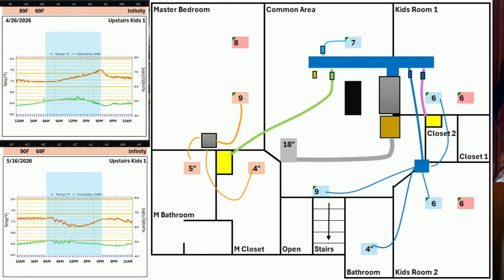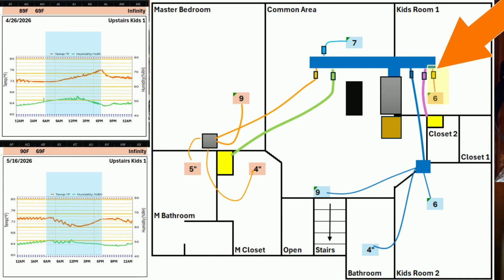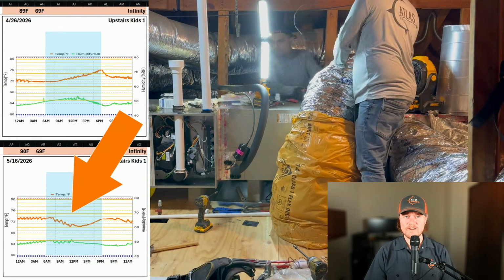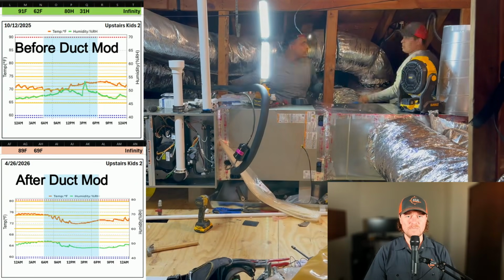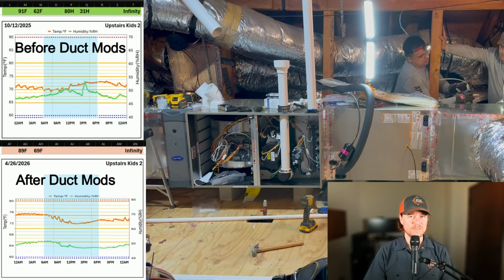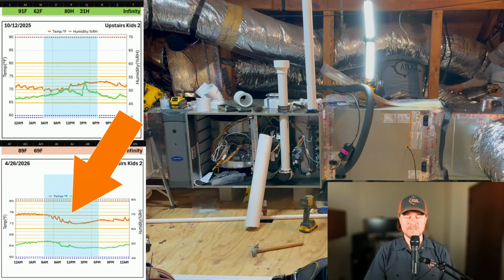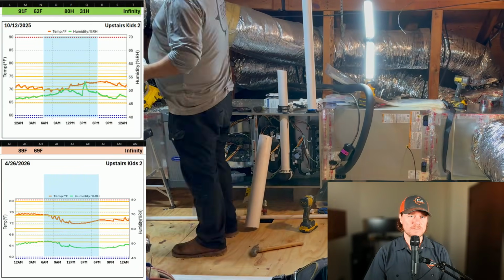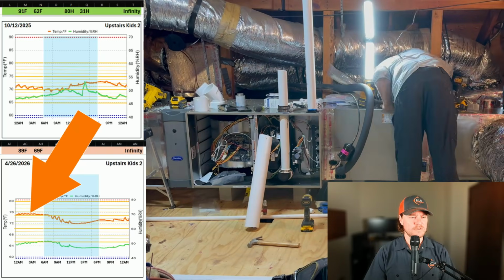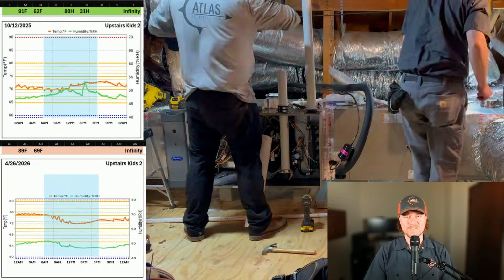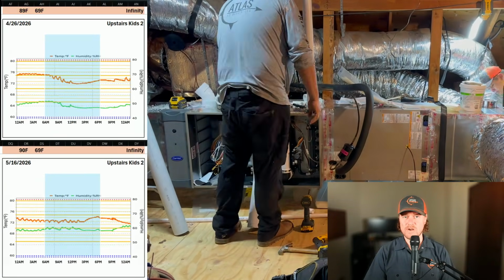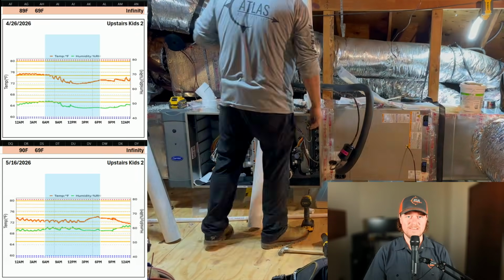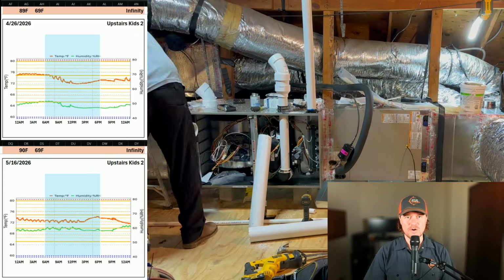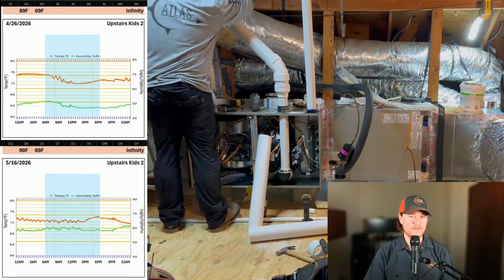What I ended up doing is rerouting that duct altogether from the distro box and connecting it directly to the supply trunk. That way I could fully utilize that duct and get the max amount of CFM out of it. And that did the trick. And in my son's room, after doing the duct modifications, it created a problem. You can see here on this day, I had the temperature set at 72 degrees, and in his room, it's getting pretty close to 76 degrees. What I ended up doing is dampering down the 9-inch over the stairwell, which is tied to the same distro box, and that directed more airflow to his room, fixing that problem. And I simply dampened it down about 50% at the vent.